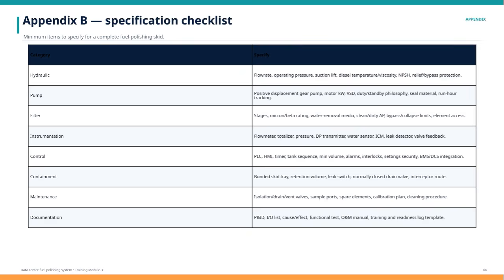Next, for the pump, we need to specify the type, such as a positive displacement gear pump, along with motor kilowatt rating, the use of a variable speed drive, the duty and standby pump philosophy, seal materials, and run-hour tracking capabilities. These details affect how efficiently and reliably the pump operates. The filter section requires specification of the number of stages, micron or beta rating, water removal media type, the pressure differential between clean and dirty filters, bypass or collapse limits, and access to filter elements for maintenance. Proper filter specification is vital to ensure effective contaminant removal and system uptime.